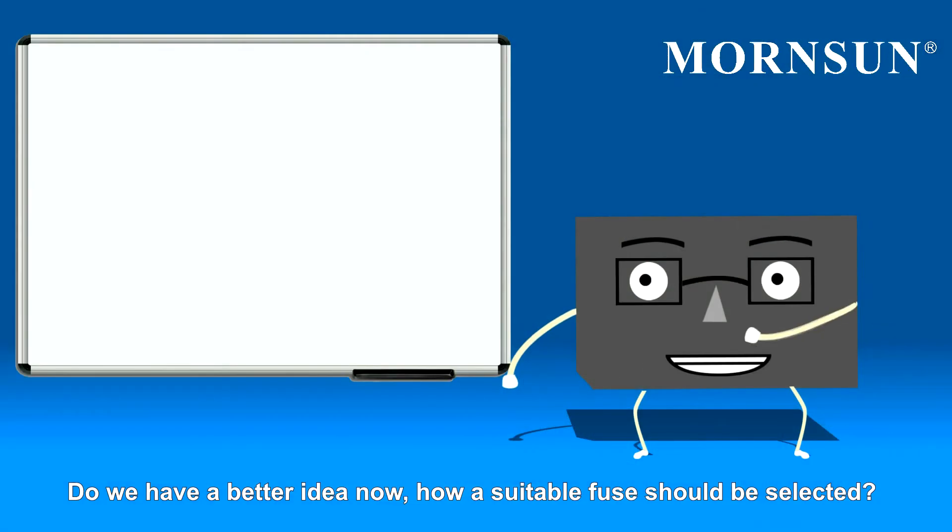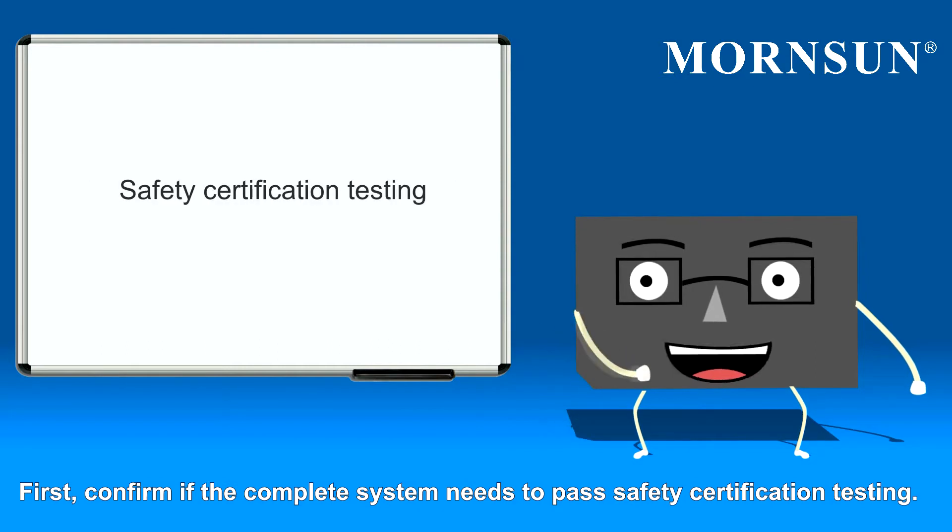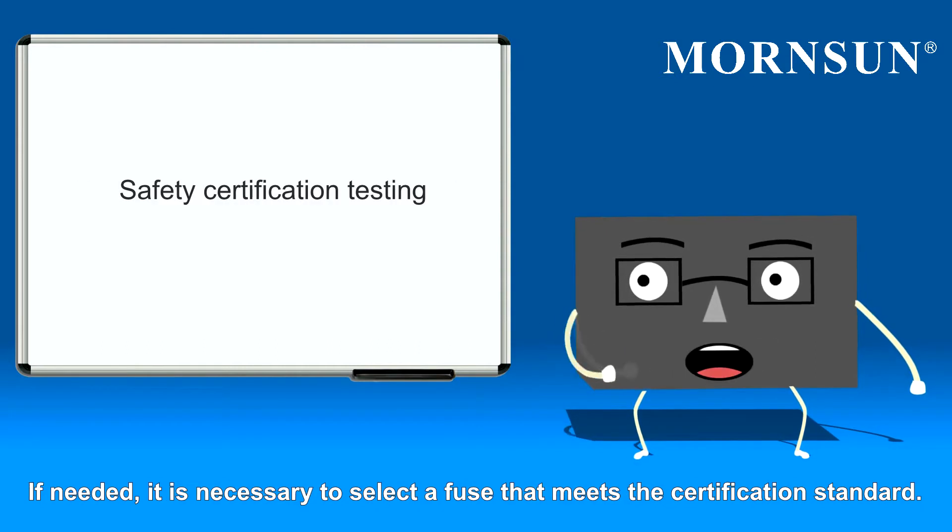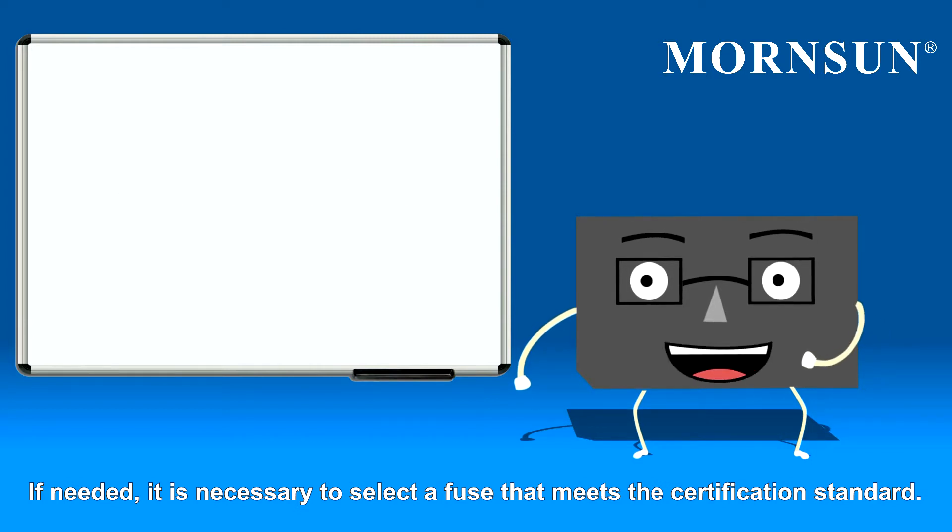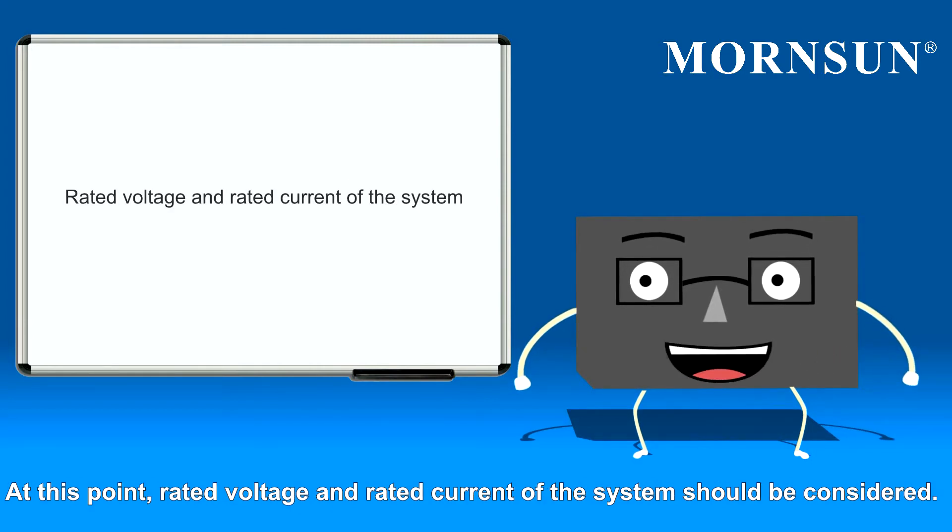Do we have a better idea now how a suitable fuse should be selected? First, confirm if the complete system needs to pass safety certification testing. If needed, it is necessary to select a fuse that meets the certification standard. At this point, rated voltage and rated current of the system should be considered.